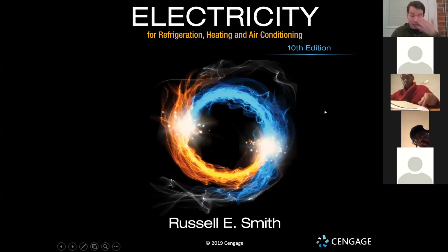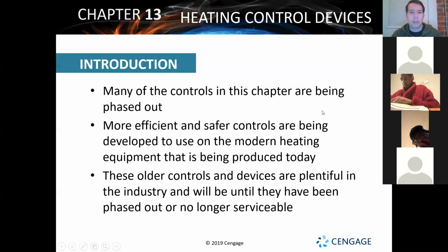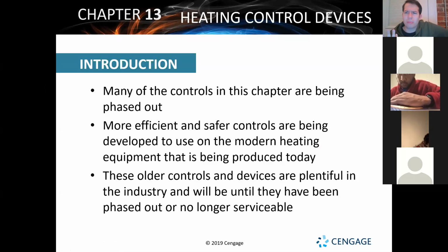So again, getting right into unit 13, or chapter 13, sorry. Heating control devices. We just ended chapter 12 talking about pretty much heat controls, heat pumps, gas furnaces, oil heat. Didn't talk anything about boilers, weirdly enough. But with heating controls, there are a number of different things we can use that are specific to the heating control side of HVAC compared to air conditioning controls.